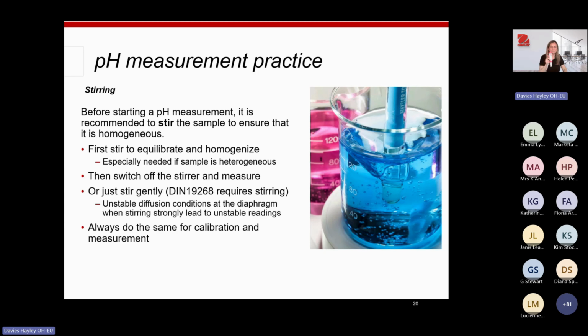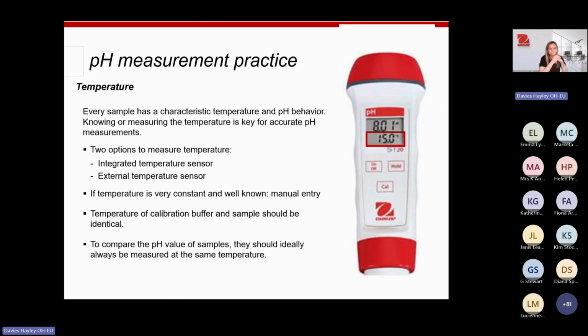By that we mean just pop your probe into the solution and give it a little stir, just like that. So not like you're cooking, stirring the chili on a Saturday night, just a little gentle stir and that should be fine. And always make sure that whatever you do for the calibration, you do for the measurement and vice versa, because it needs to be consistent in the way that you're taking your measurement samples.